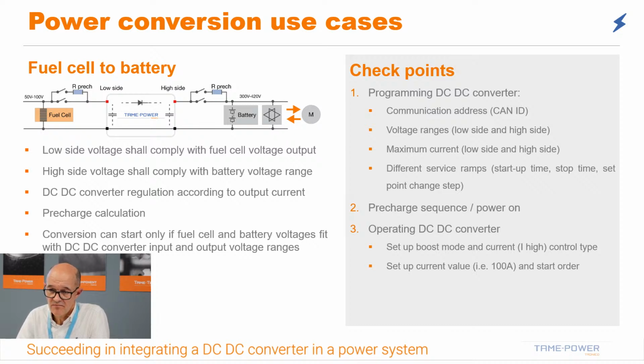This is a very simple use case, but it's an unusual use case on which we have many applications at the moment. If you want the current to be changed, you just have to resend a new CAN frame requesting the converter to feed 50 amps instead of 100, and according to the slope and reaction time previously given to the converter, it will apply that and change the current from 100 to 50.